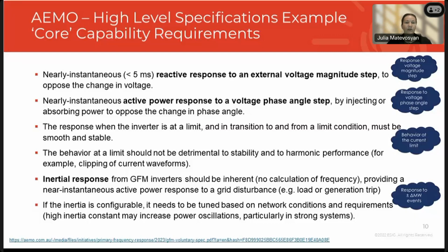So they're requiring nearly instantaneous reactive response to external voltage magnitude step. So this is the voltage magnitude step response, active power response to voltage phase angle step, and response when the inverter is at limit, and transition to and from the limit condition must be smooth and stable. That is basically saying not to have any jerky behavior as you switch from operating at the limit back to operating under the limit. So this is as much as how behavior at the current limit is described. The behavior should not be detrimental to stability or to harmonic performance. Inertia response from grid forming inverters should be inherent, so not waiting for measuring frequency and then responding, and then providing nearly instantaneous active power response to grid disturbance. So this is the response to megawatt loss.